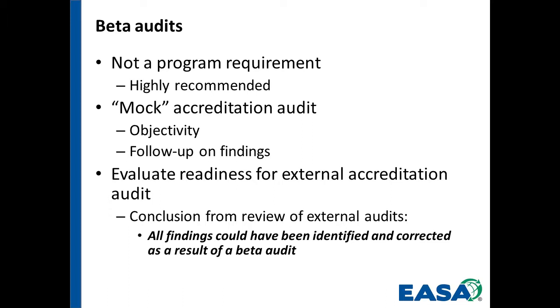Beta audits are not a program requirement, but highly recommended. I can't emphasize enough how important it is to do these beta audits. When you do these audits, whatever you find, treat it with objectivity and follow up on the findings, and particularly in the calibration areas, make sure that things are calibrated. Say there's a finding where one of the checks is with the tachometer, checking the speed on the no-load run test. If somebody's not following that, or if it's not in your documentation, modify your documentation and add that to your document so that it's known that you're going to do that test.